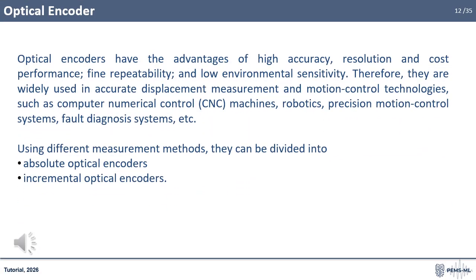Optical encoders have the advantages of high accuracy, resolution, and cost performance, fine repeatability, and low environmental sensitivity. Therefore, they are widely used in accurate displacement measurement and motion control technologies, such as computer numerical control machines, robotics, precision motion control systems, fault diagnosis systems, etc. Using different measurement methods, they can be divided into absolute and incremental optical encoders.